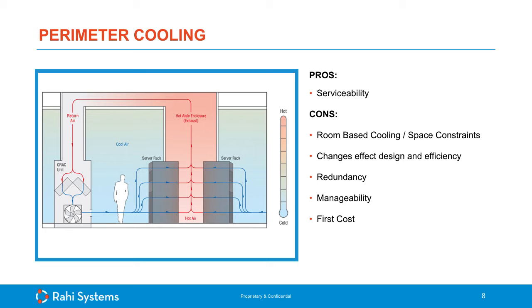Also, perimeter units are not considered close coupled, obviously. They are not close coupled to the IT load, but they're easy to service, so that's definitely one of the pros. Serviceability, and they maintain the load that way. However, in many cases, they tend to take up valuable IT space, or what we call white space. Once built in and designed in, there's less opportunity to add or change the design without a major retrofit. And there tends to be a higher first cost and a higher construction cost as well when compared to other types of cooling.